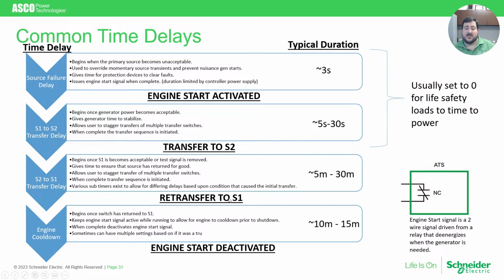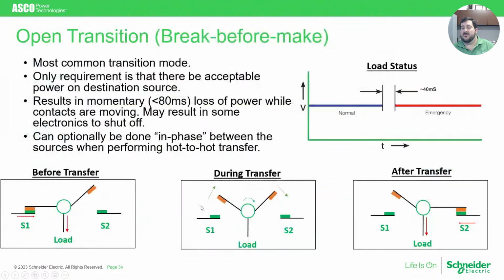The last step we take is to run the generator for a short period after disconnecting from it to ensure it has time to cool down properly before shutting it off for good. And you got to make sure to coordinate that with your generator controller to make sure you don't accidentally have two cool down periods running back to back to each other.